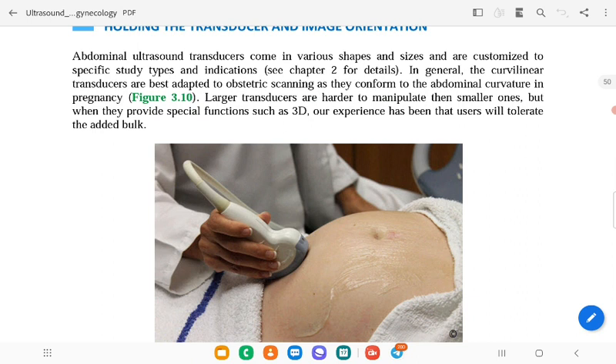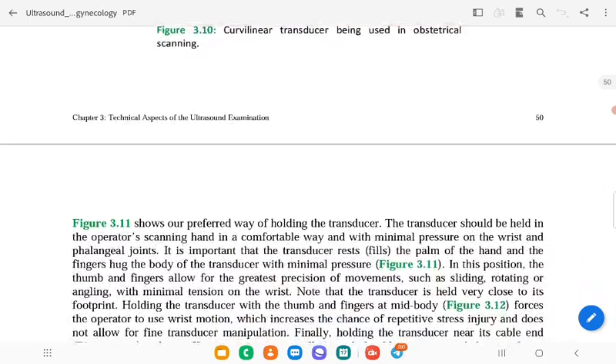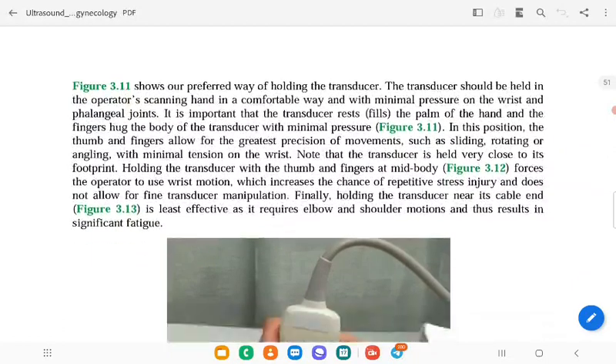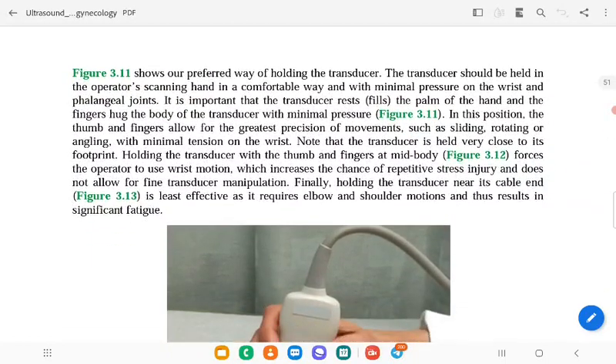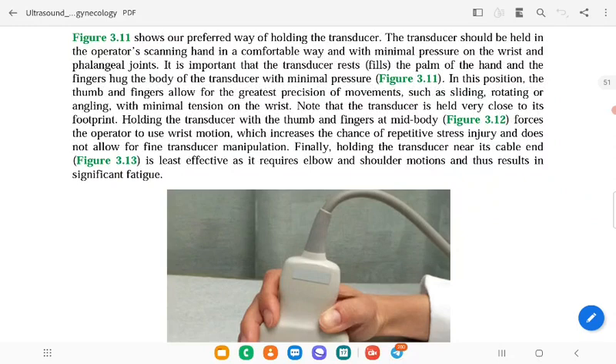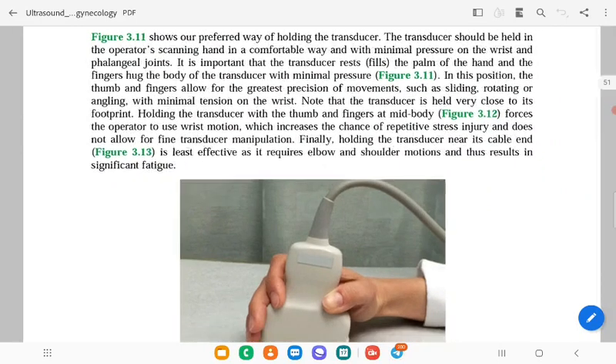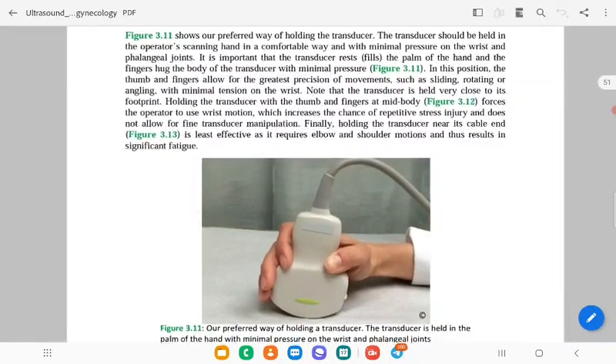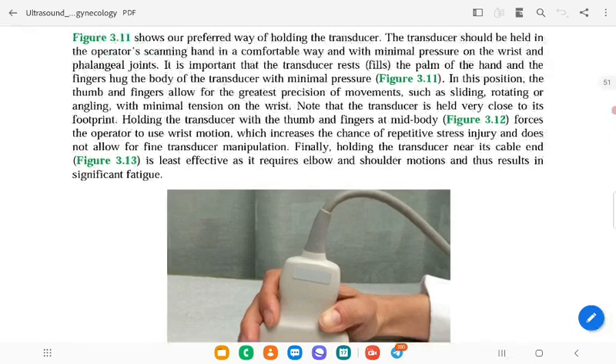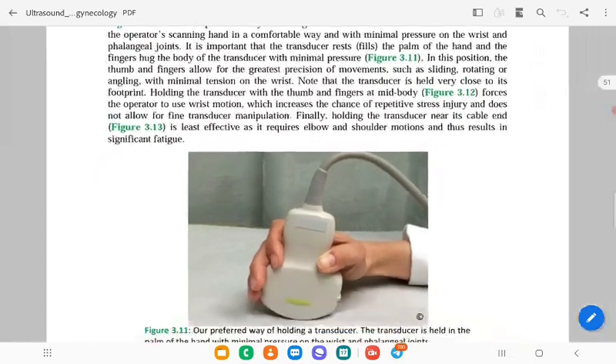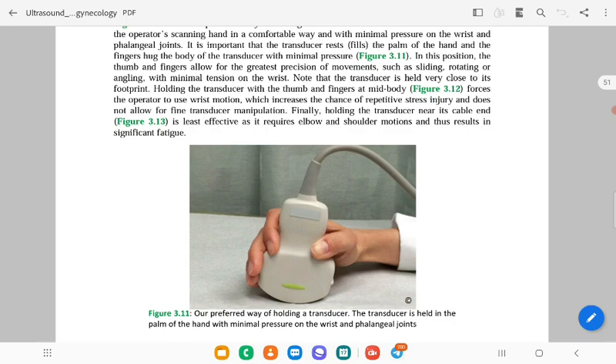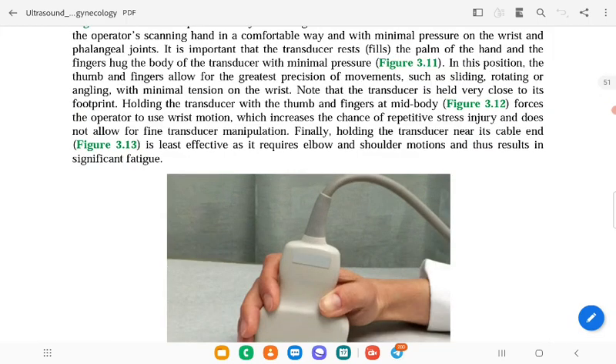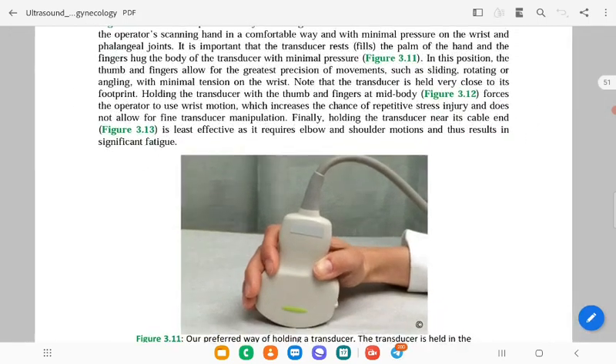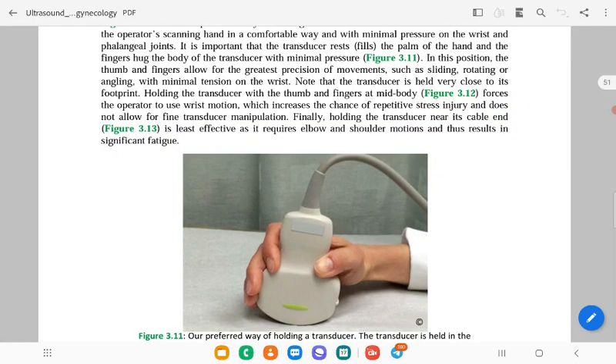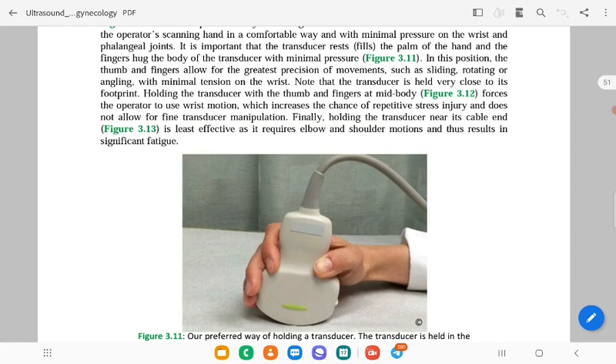but they provide special functions such as 3D. This is the figure showing how we are holding the transducer. The transducer should be held in the operator's scanning hand in a comfortable way with minimum pressure on the wrist and phalangeal joint. It is important that the transducer rests on the palm of the hand and the fingers on the body of the transducer with minimal pressure.